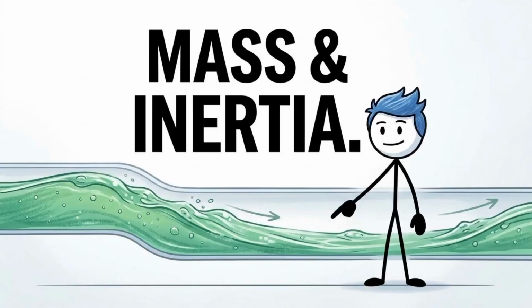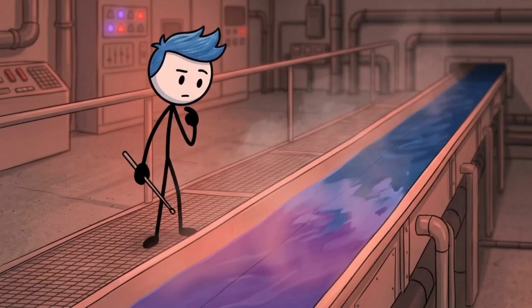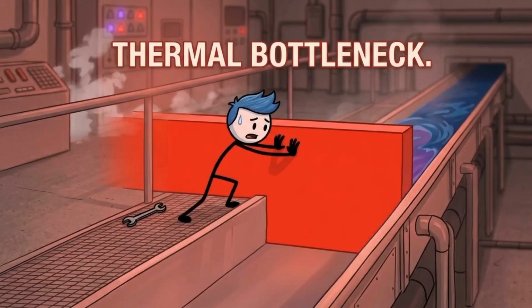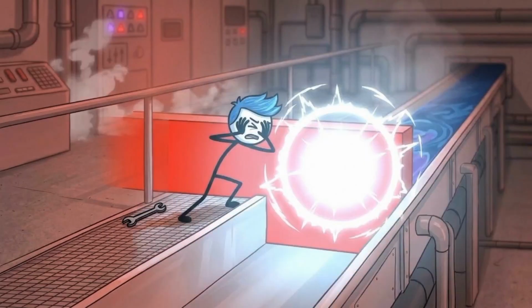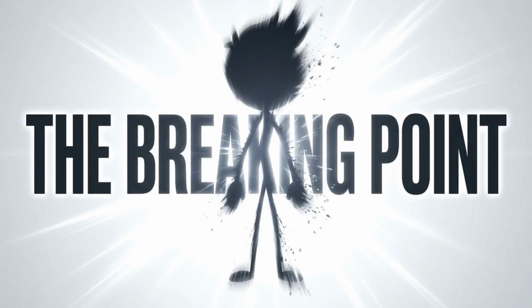But water has mass, it has inertia. If heat begins entering the cooling system faster than the cooling system can carry it away, a localized thermal bottleneck develops. The heat literally piles up at the copper interface faster than the water can sweep it out. Which brings us to the breaking point.